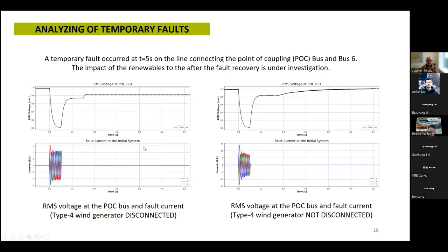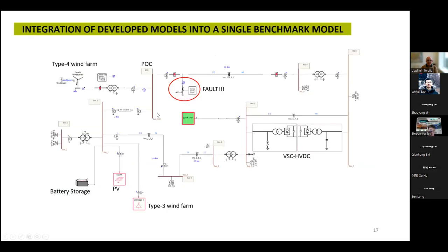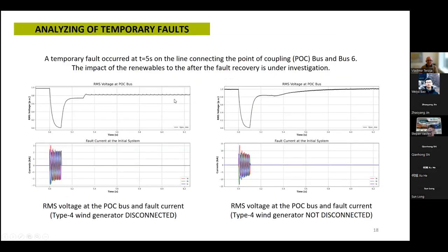following the fault, the type 4 wind farm and the faulty line are disconnected from the grid. I mean this wind farm and this transmission line. The fault is eliminated and the line after reclosing is successfully reconnected, but the type 4 wind farm is still disconnected. It can be seen that with the loss of generation, even after reclosing the line, the bus voltage is not fully recovered.